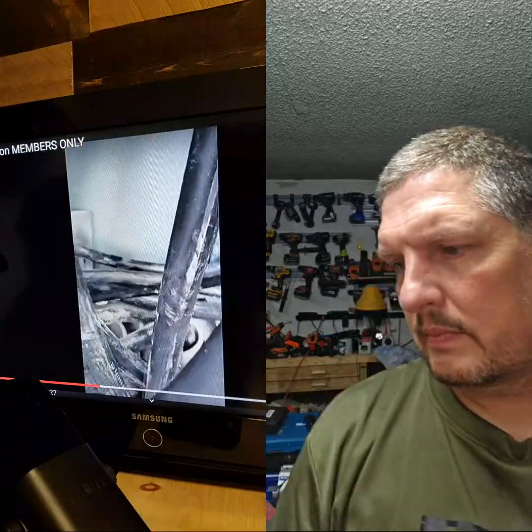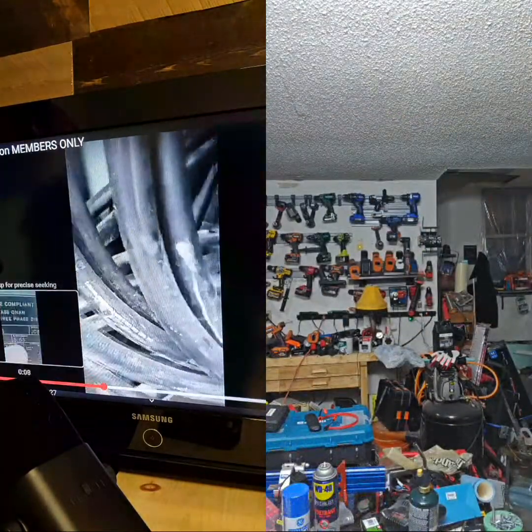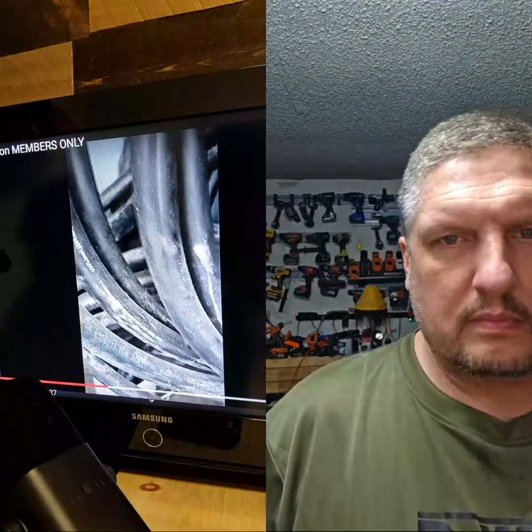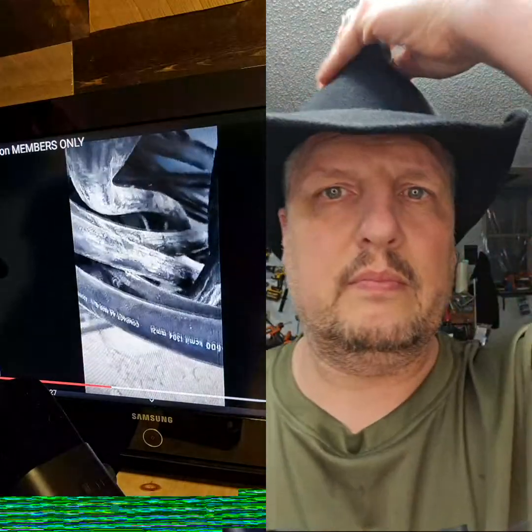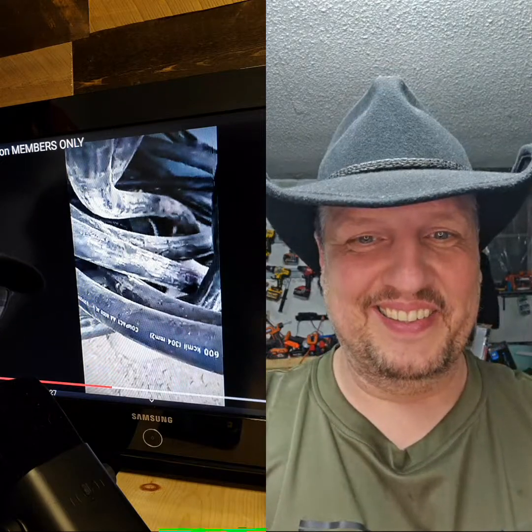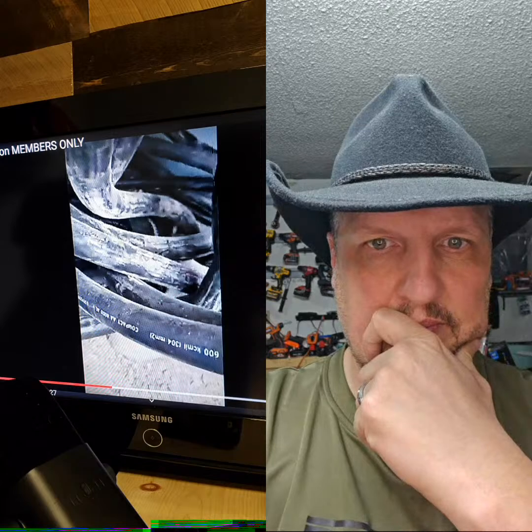And what the amperage is, and make sure that we have the correct amount of wire here. There's 600 kcmil. Those wires are about that big each. They're fairly large, right? In a minute, I'm going to show you the code book. They're good for 340 amps each. So they've got 5 of them in a set. They land all in the same manner at the same location. It's called a parallel set. You can multiply that by 5, and that'll get you your total amperage.